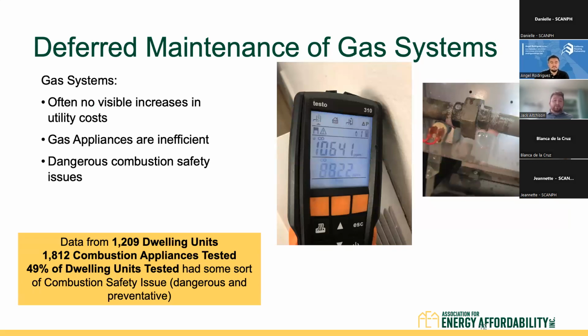So moving on to gas, with deferred maintenance of gas systems you're probably not going to see that in your utility bills, for two main reasons. One, gas is less expensive as a fuel type. In addition, gas appliances are already fairly inefficient. Peak efficiencies of gas systems are around 95%, but most people with standard gas appliances are in the range of 65 to 80%. If you defer maintenance on gas systems, you're probably going to see a drop of 5, maybe 10% in efficiency, whereas for electricity, you could go from 300% down to 100%. That's going to be a significant drop.